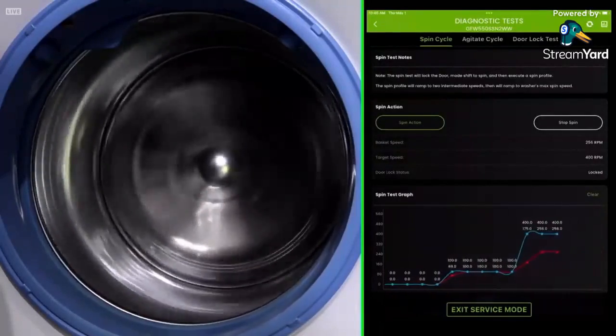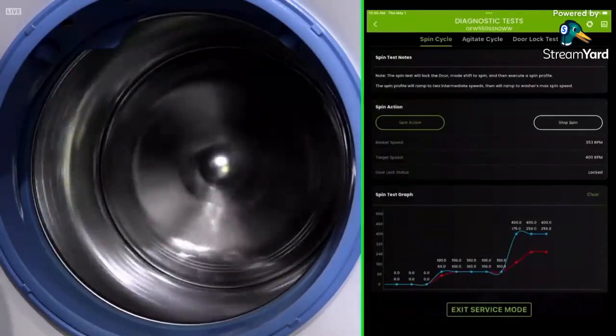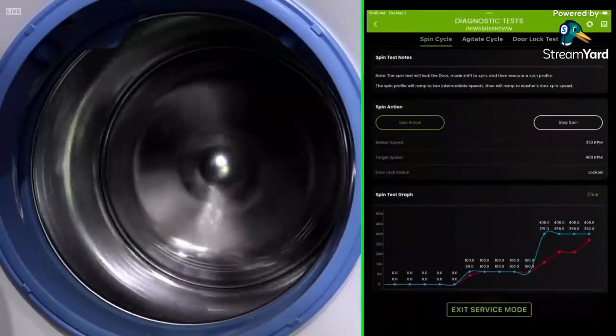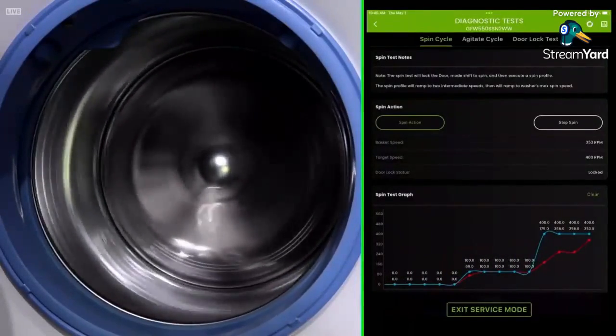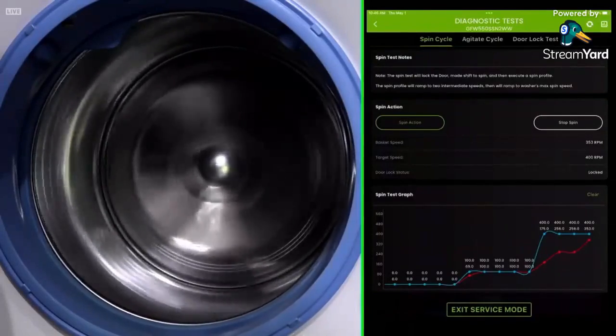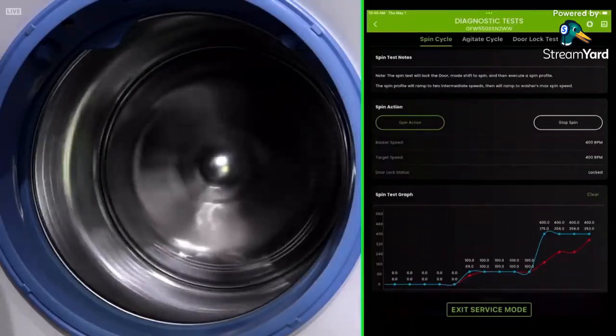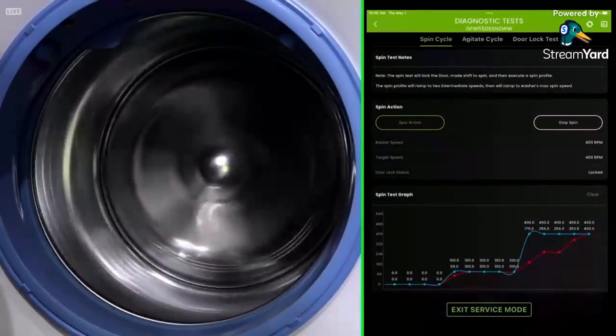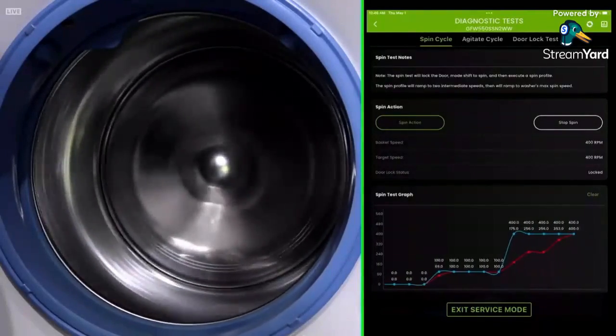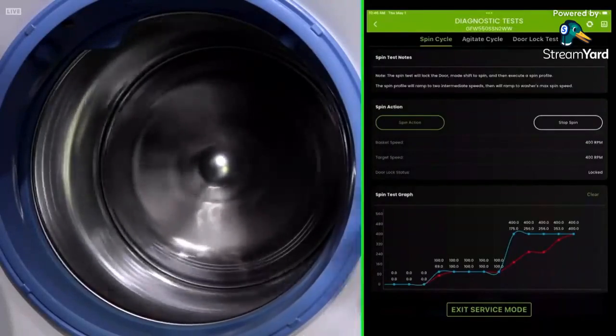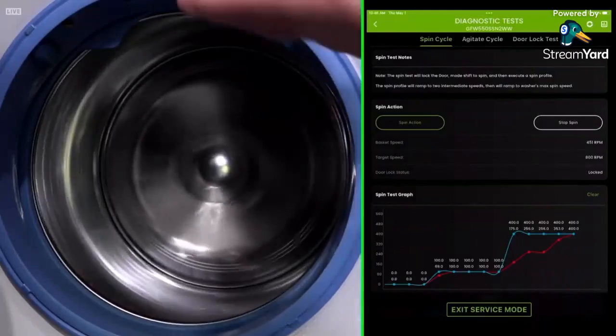250, let me see if I can do this, 256, yep. So the target speed is 400, but the basket is at 353. And now it's reached 400. It's going to stay there for a little bit because it needs to be comfortable and make sure the machine isn't shaking.